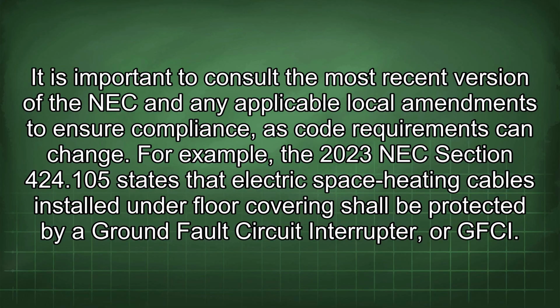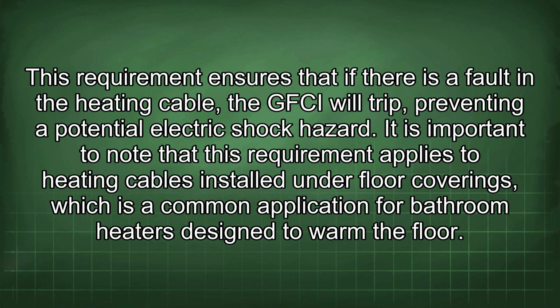For example, the 2023 NEC section 424.105 states that electric space heating cables installed under floor covering shall be protected by a ground fault circuit interrupter, or GFCI. This requirement ensures that if there is a fault in the heating cable, the GFCI will trip, preventing a potential electric shock hazard. It is important to note that this requirement applies to heating cables installed under floor coverings, which is a common application for bathroom heaters designed to warm the floor.